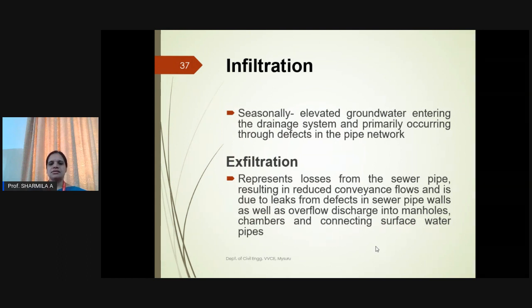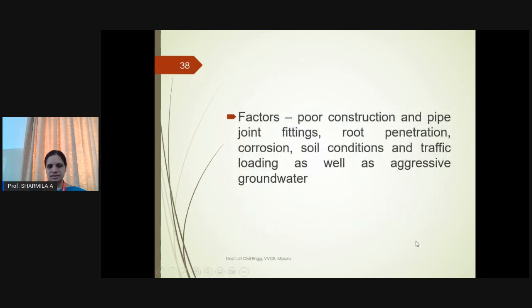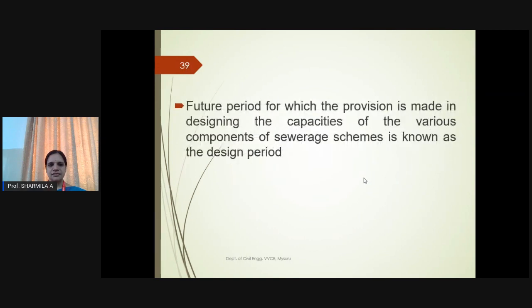Groundwater infiltration and exfiltration are also major factors. Infiltration depends on the nature of soil, sewer material, type of joints, workmanship in laying sewers, and position of the underground water table. Infiltration adds water to the wastewater quantity seasonally due to elevated groundwater entering the piping system and defects in the pipe network. Exfiltration results in losses from pipeline walls, leakages, and overflow into manholes. Other factors include pipe joint fittings, root penetration, corrosion, soil conditions, and traffic loading.